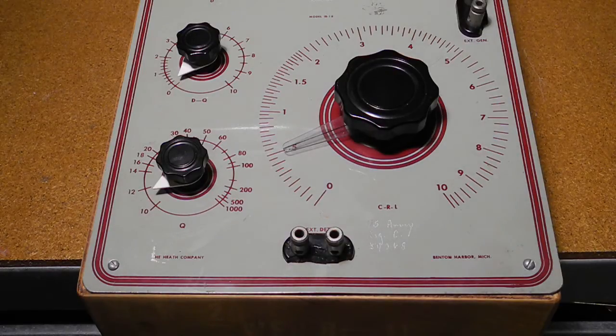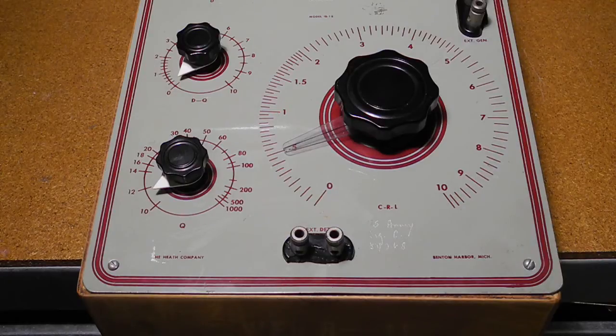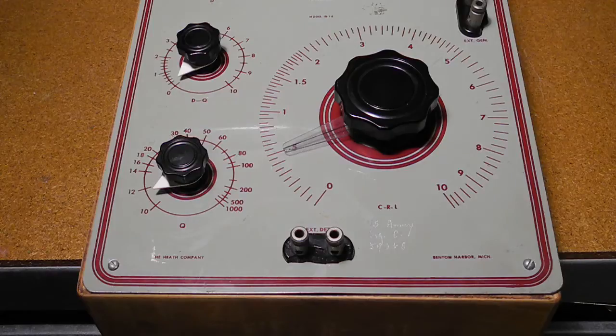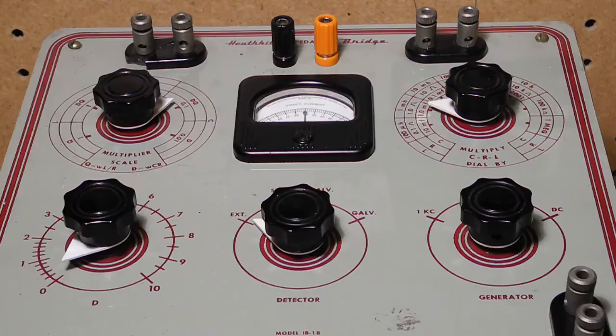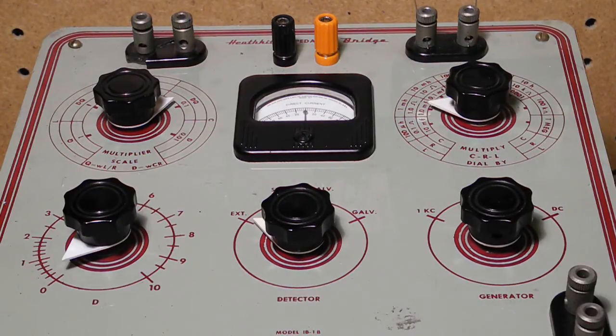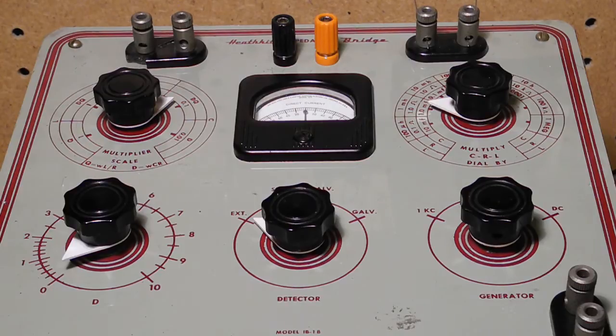It uses a meter for indicating bridge balance when measuring resistance, and external headphones, which were not included, when measuring inductance or capacitance. For DC measurements, it uses an internal 6-volt battery. For AC measurements, it uses an internal 1 kHz oscillator using a device called a Hummer. It can also make measurements using an external signal generator.